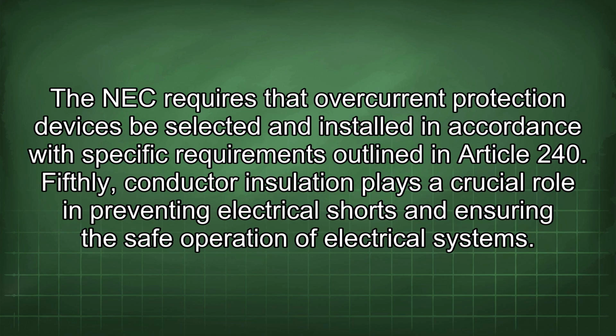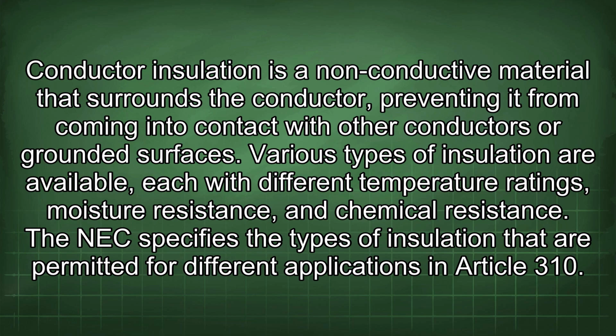Fifthly, conductor insulation plays a crucial role in preventing electrical shorts and ensuring the safe operation of electrical systems. Conductor insulation is a non-conductive material that surrounds the conductor, preventing it from coming into contact with other conductors or grounded surfaces. Various types of insulation are available, each with different temperature ratings, moisture resistance, and chemical resistance. The NEC specifies the types of insulation that are permitted for different applications in Article 310.